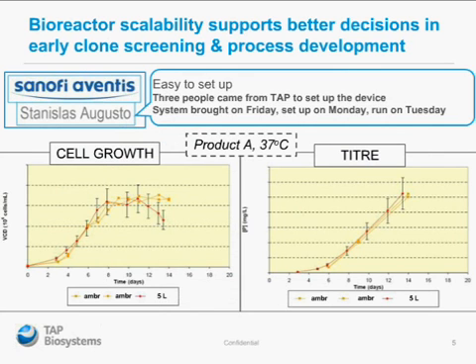This is an experiment I actually ran myself at Sanofi Aventis in Paris. We took the ambr in on a demonstration and looked at running duplicate ambr vessels in parallel against a five-litre Sartorius reactor running at the same time in a fed batch culture. The error bars shown are plus or minus 20% acceptance criteria on the system, and the ambr did very well. Stanislas also said that it's easy to set up — three people from TAP came to set up the device. It was brought on Friday, set up on Monday, and run on Tuesday. It demonstrates that it's possible to drop the ambr into your laboratory and get these kind of scalability results straight away.